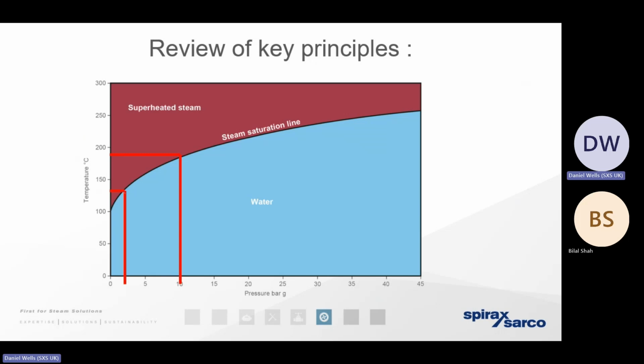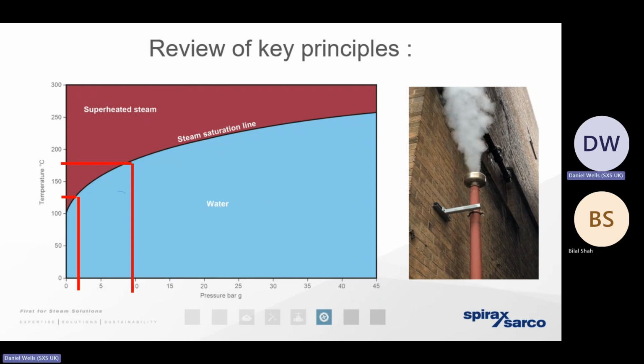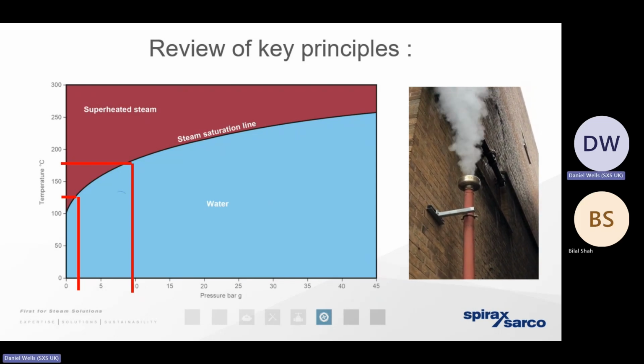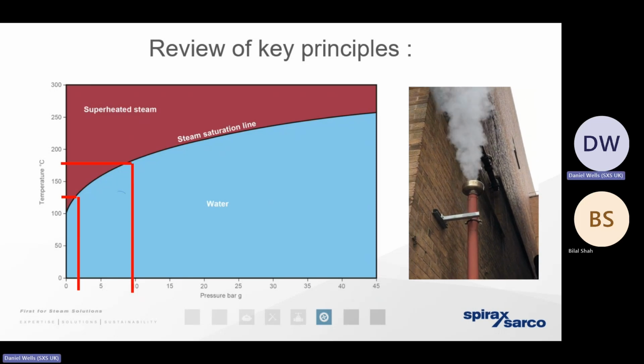That tells us that when the condensate, when that liquid is under pressure within the pipe infrastructure, it can exist as a liquid at 184 degrees. But we know that if we drop the pressure down, that liquid cannot exist at 184 degrees at 0 bar gauge, for example. So if we think back to that failed steam trap, we've got two things happening. We've got the steam that is depressurizing and expanding. We've got the liquid condensate that is depressurizing. And as that condensate depressurizes, a certain mass, a certain percentage, needs to boil off and expand and change state back to steam again. So that rate of expansion is going to be even greater. And that really explains why we need to vent that steam away, to prevent that vibration taking place, that damage taking place in a very, very small infrastructure.